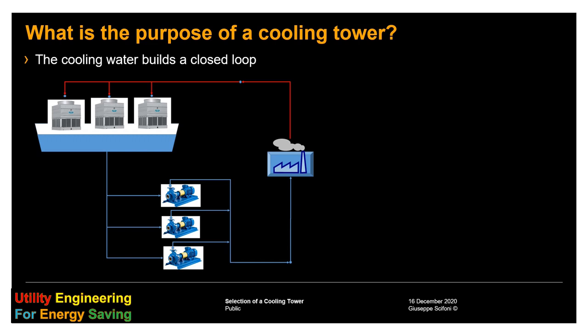There are many other ways to cool a water flow, but the specialty of the cooling towers is that no refrigerant is needed, no compressors, and therefore less power than for chillers. On the other way, the cooling temperature which can be achieved depends upon the ambient conditions. The water gets consumed and requires treatment.